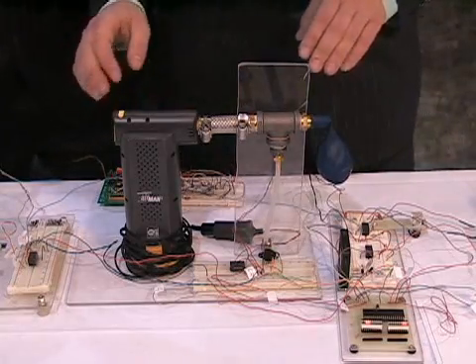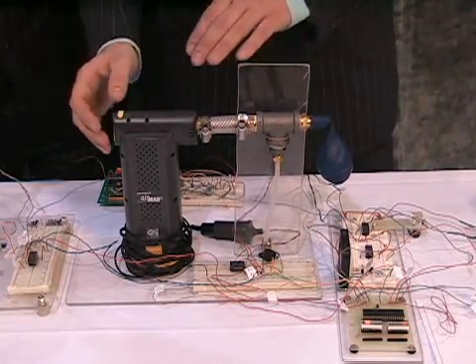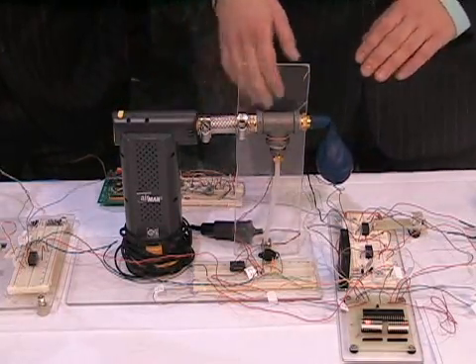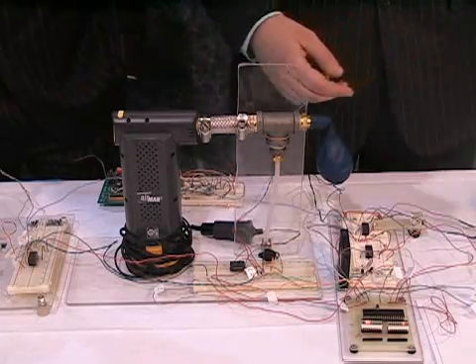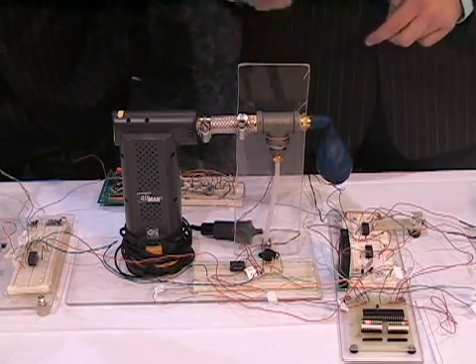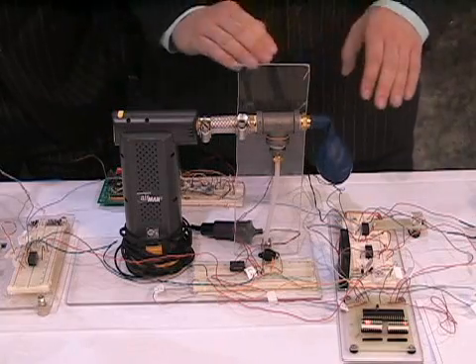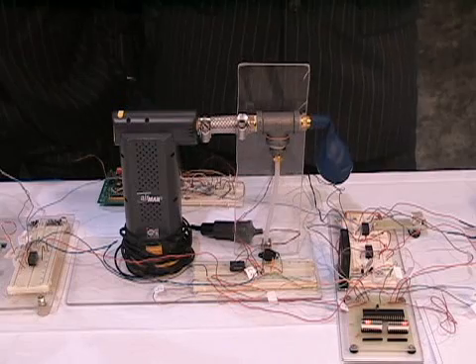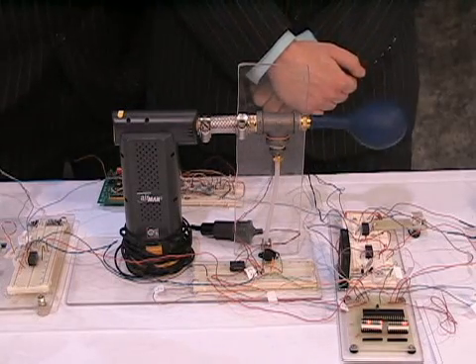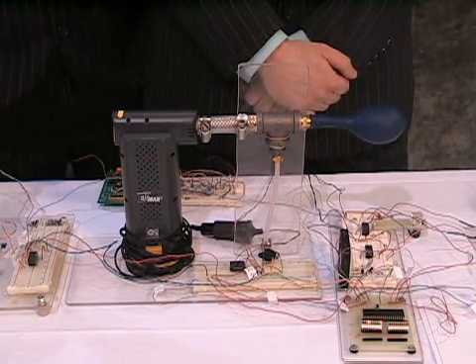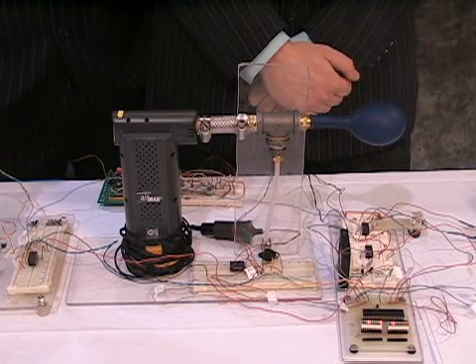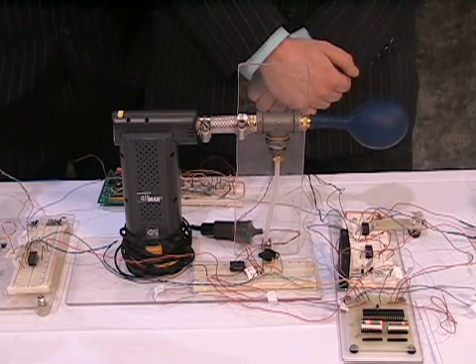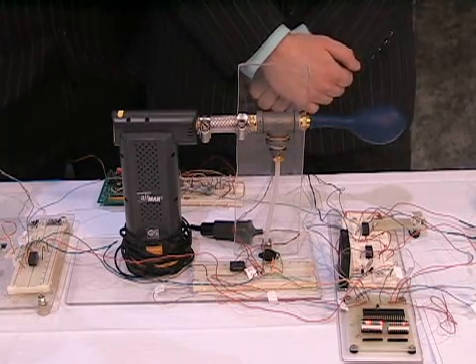And another system I want to show you here is the air pressure system. So it's set to off right now. When Tim turns it on over on the master side it's going to start sending the air pressure through. When the level gets above a hundred then it's going to shut off and let it leak out until it falls below, turn it on again to maintain a constant pressure. Okay, so now I can shut it off Tim.